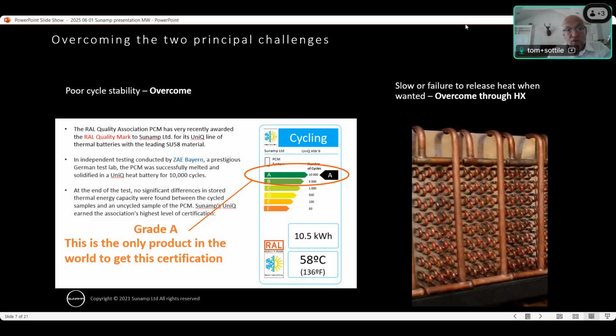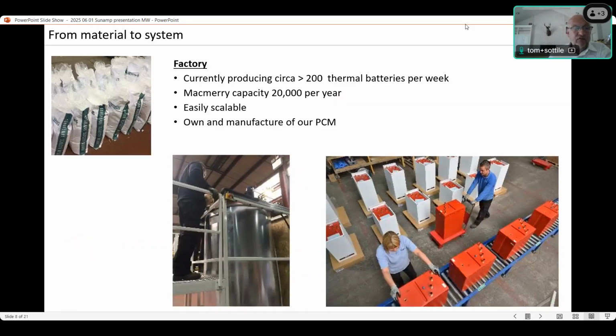The second challenge is that the phase change material tends to be a better insulator than conductor of thermal energy. So we need to develop a very high power heat exchanger that can recover the heat from the phase change material instantaneously, in a way that we can raise the incoming water from 40 degrees Fahrenheit up to 130. Solving these two problems led to the commercialization of our products that we call thermal batteries.